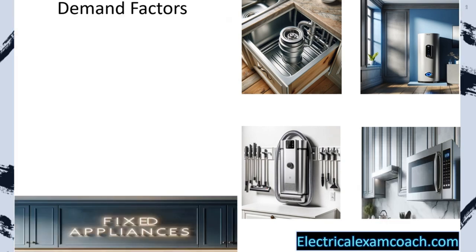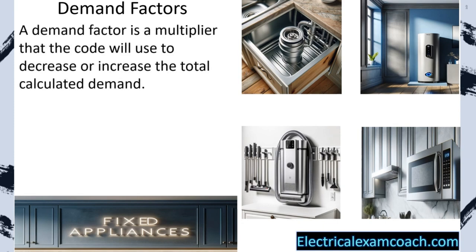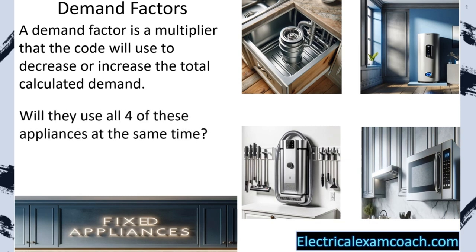Before we dive into the calculations, let's learn about demand factors — we're going to be using them for the rest of the program. A demand factor is a multiplier that the code will use to decrease or increase the total calculated demand. The code makers recognize that you won't be running all four appliances at the same time, so they've made multipliers that allow us to reduce the demand we calculate. If we have fewer amps, we can have a smaller service, smaller pipe, smaller wire, and a smaller overall cost.